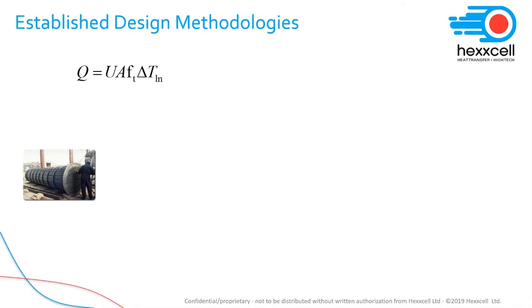Established design methodologies have not progressed much since Q equals U A delta T log mean, where U is the overall heat transfer coefficient and A the heat transfer area. What typically happens, for example in the process industry, is that the process engineer decides the inlet and outlet conditions needed from a heat exchanger with a specific duty. The heat exchanger designer receives this specification and designs a heat exchanger with a certain area A. The problem is that when the heat exchanger is put into operation, it starts fouling.